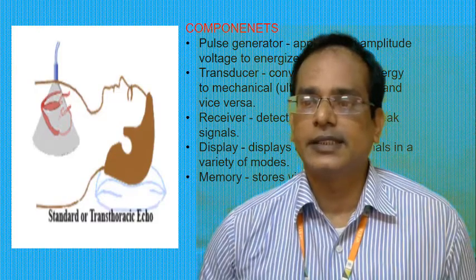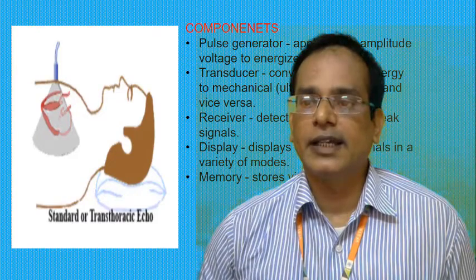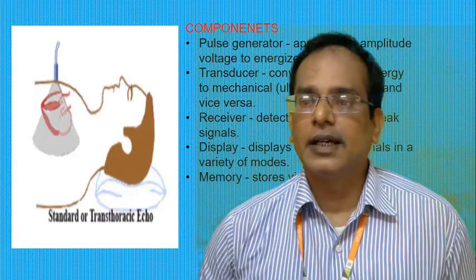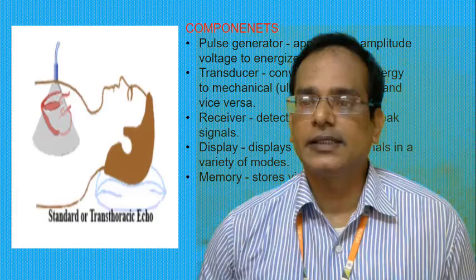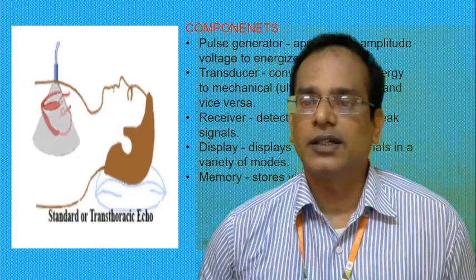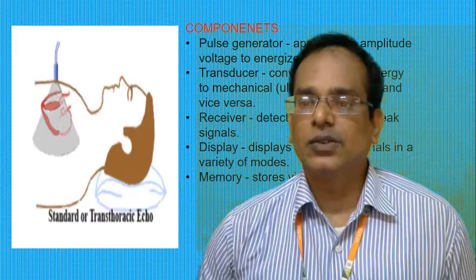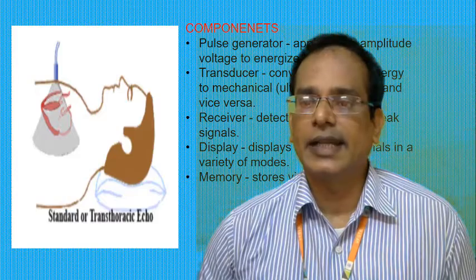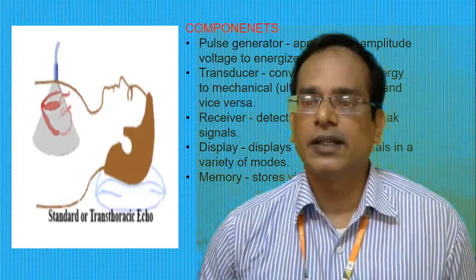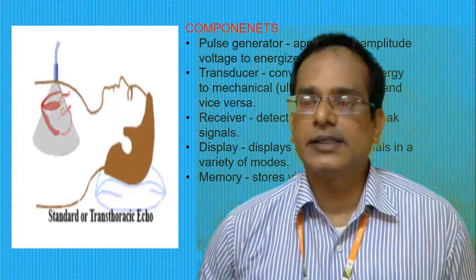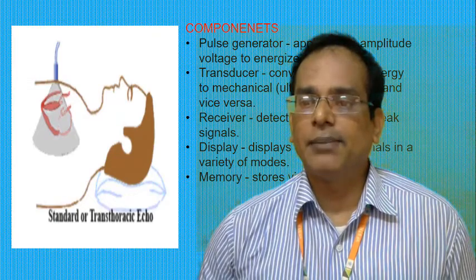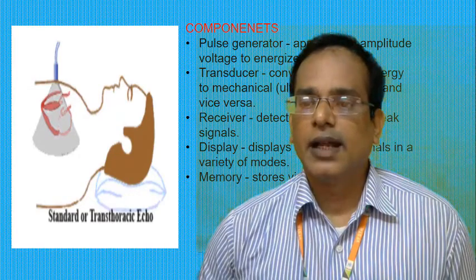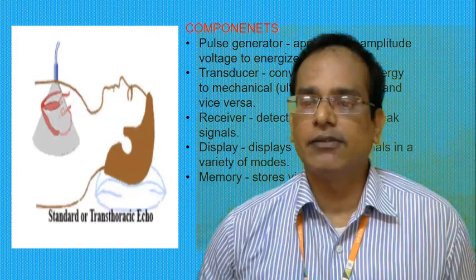ultrasound energy. Also, the reflected energy is converted back into electrical energy with the help of the transducer. This is called vice versa, information is obtained with the help of the transducer. So the transducer has a transmitter as well as a receiver. The receiver detects and amplifies the weak signals, and after that it is given to the display.